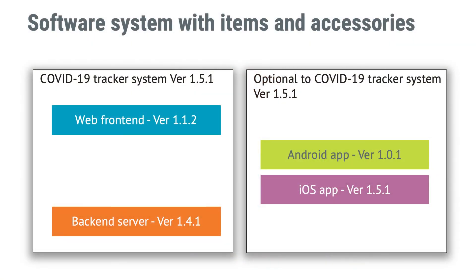I strongly recommend you invest time in defining your software system accurately. It is essential to understand the boundaries of your system to manage software risk management, future releases, and maintenance properly. The example we just looked at could look completely different depending on how you define your software system. The front-end and server might work as a software system on their own, with the apps being optional. The same goes with embedded systems — a software tool to read engineering data from a USB port does not need to be part of your medical device software system. IEC 62304 does not give directions about this, but you may find guidance in regulations.